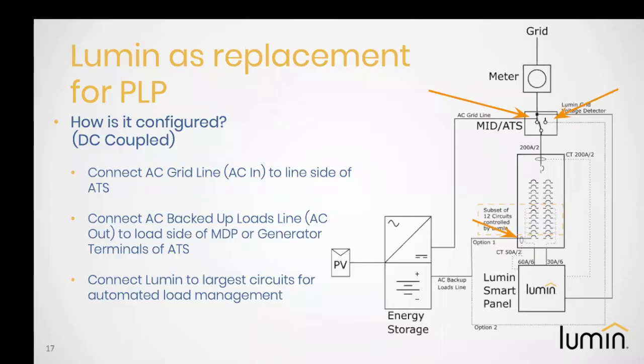When the grid goes down here, the transfer switch will redirect the loads from the grid tied connection to the PV battery connection only. So Lumin, I'd say, is especially important to these installations as that single inverter output often has a more limited continuous power output or amperage limitation than some of those larger AC coupled systems. So it's extra critical that we're governing those largest loads, protecting that battery system and the inverter during that outage. So those are the 3 system configurations that I wanted to make note of.